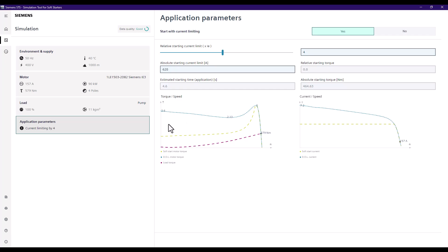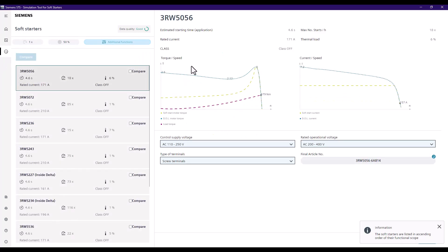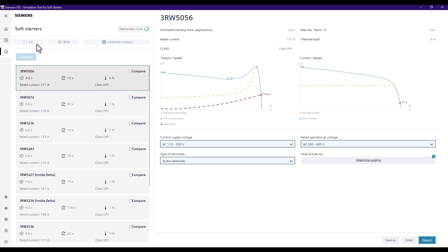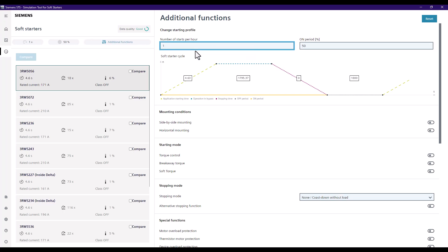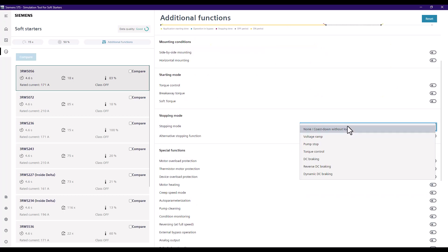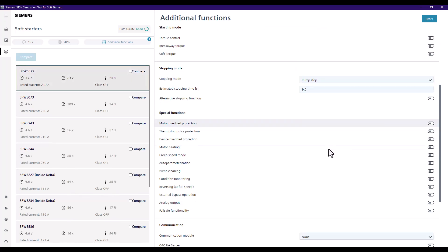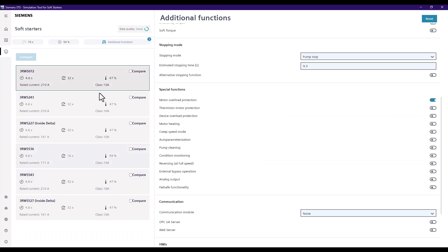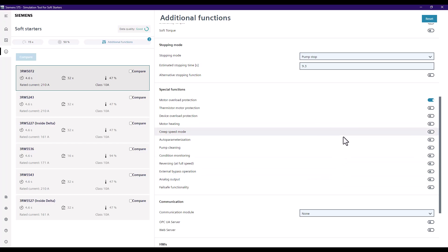The results selection shows a number 10, meaning we've got 10 different options to pick from at this stage, but we can refine those results further. Under the additional functions we can set how many starts per hour we want — let's say 15 times per hour. Given that we're pumping, we'll add a pump stopping function and define the stopping time. We can also select motor overload protection, which reduces our options.